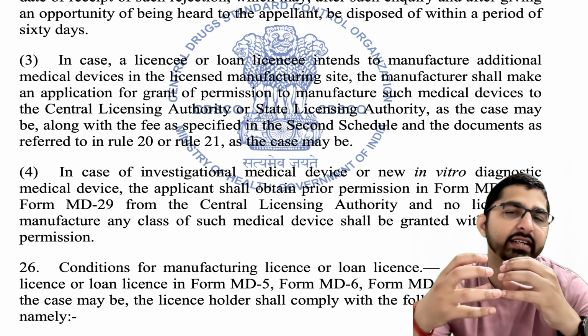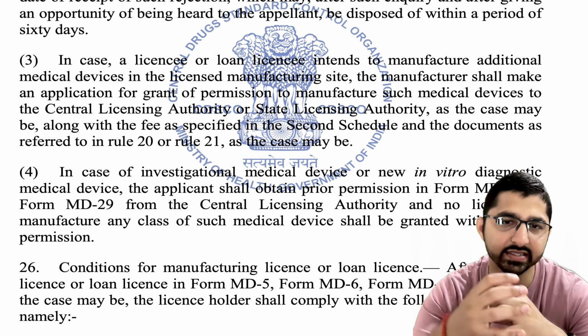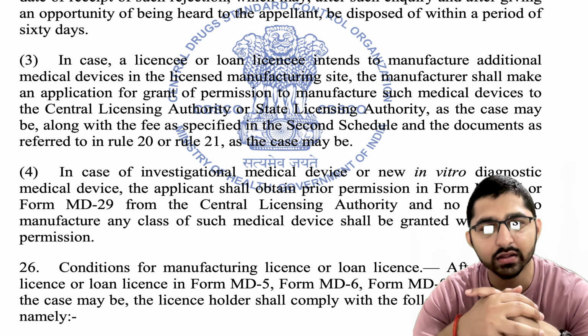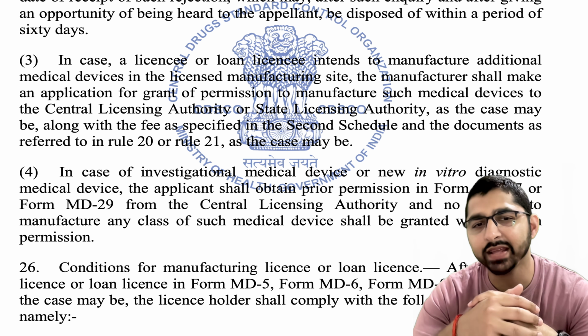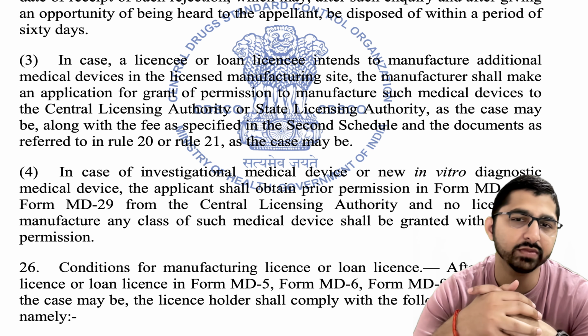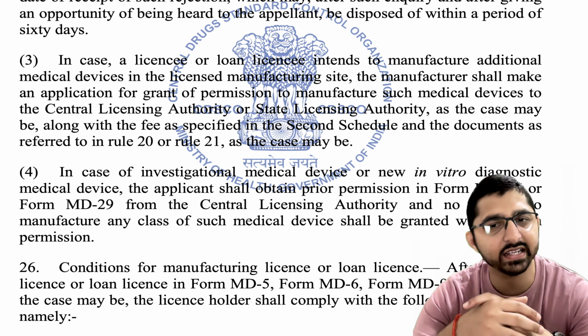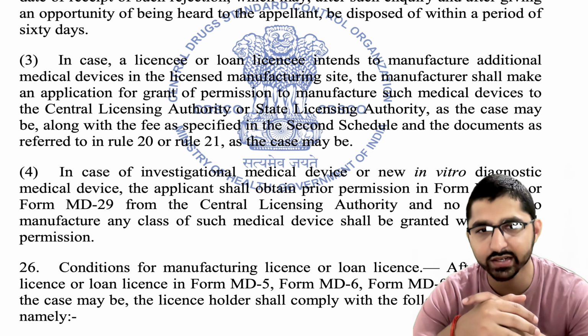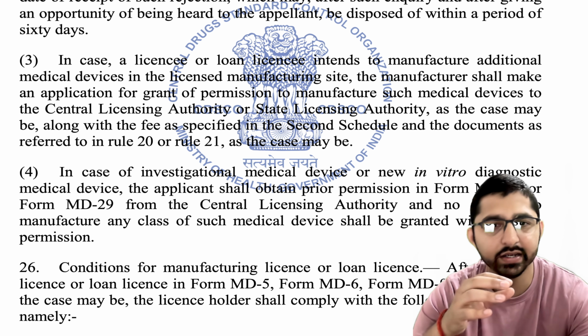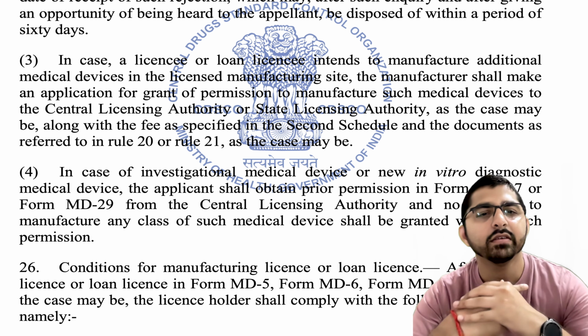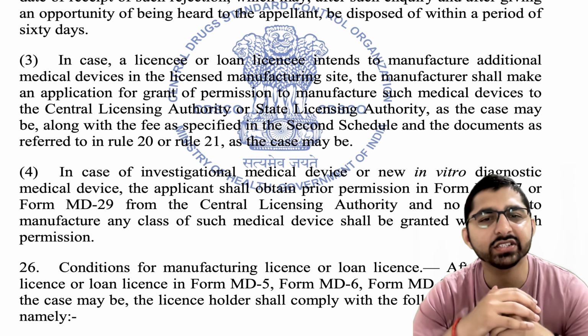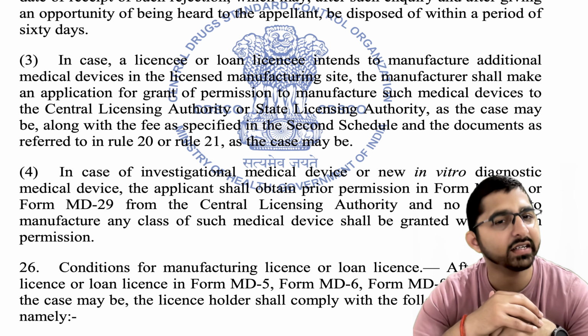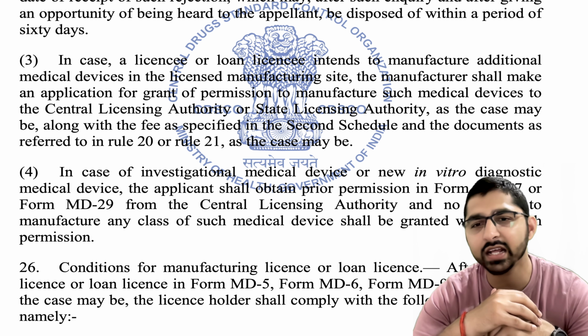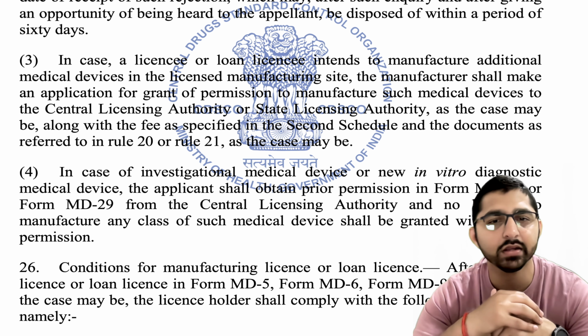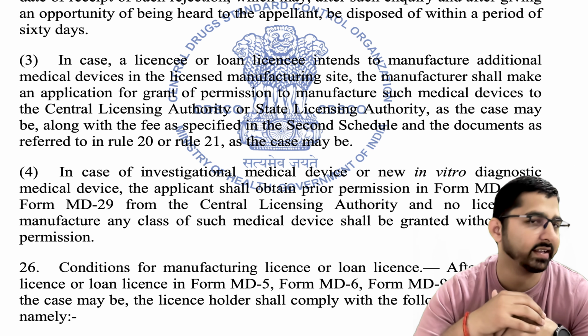In case a license or loan license holder intends to manufacture additional medical devices in the licensed manufacturing site, the manufacturer shall make an application for grant of permission to manufacture such medical devices to the CLA once again with the required fees. Right? Whereas in case of clinical investigation of medical devices or new invitro diagnostic medical devices, the applicant shall obtain prior permission from the CLA in form MD27 or MD29.